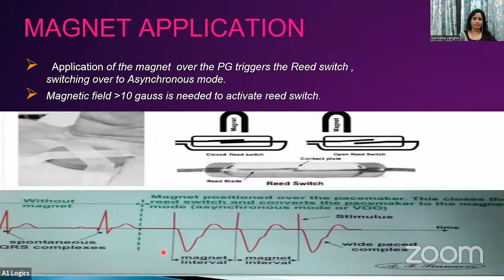Now, two things you have to know in this. One thing, with this magnetic application, we cannot be sure that it is the same in all the models. It can vary depending upon the manufacturers. If you apply the magnet on the pacemaker, it will be converted to the asynchronous mode. Second, if the patient is having an ICD, placing the magnet over the ICD will terminate only its tachyarrhythmia detection and anti-tachycardia function, and not the pacemaker function. So for a patient with an ICD, only reprogramming should be done.